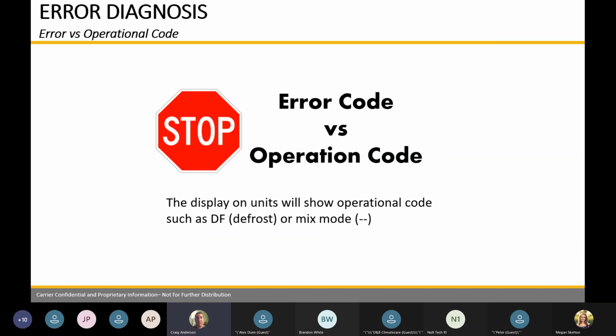Error codes and operation codes. So there's two on the unit. You're going to get an error code if something is going wrong. Your unit is also going to have operation codes. So when they turn on their unit or turn off their unit, it's going to flash a little code like CF, or you're going to get a DF if the unit is in defrost. The unit is actually going to give a code. Two lines is mixture mode. If you have a multi-zone unit and they try to put heating on one and cooling on the other, it's going to give you two lines. They can't operate like that. So you have to figure out what's an operation code and what's an error code. So if a customer calls you and says, I got DF coming up all the time, but the unit's running, stuff like that, read the manual, see what the operation codes and the error codes mean.